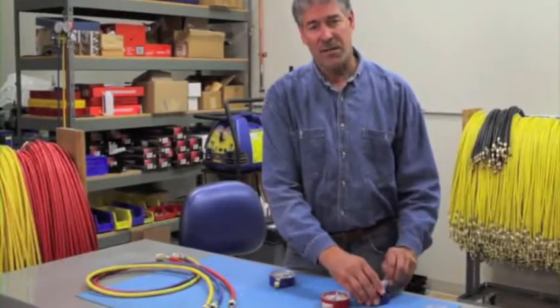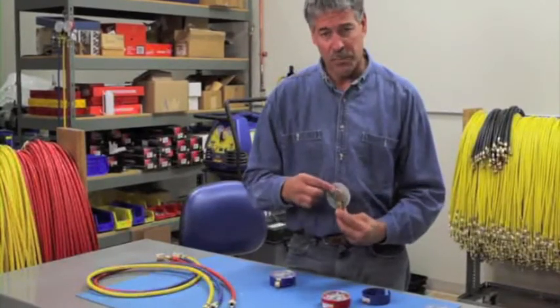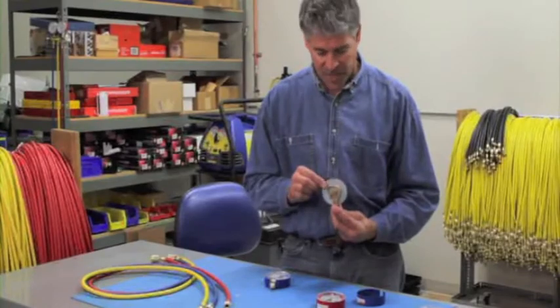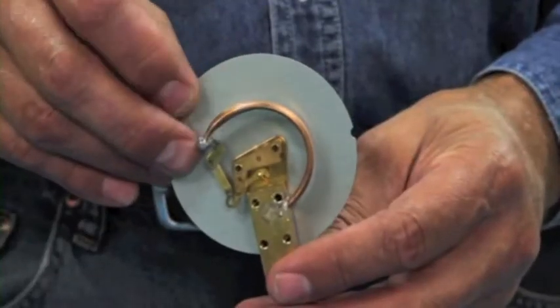When a gauge is overpressurized, the bourdon tube becomes damaged when it goes outside the working pressure of the gauge, as demonstrated by this bubble in the tube.